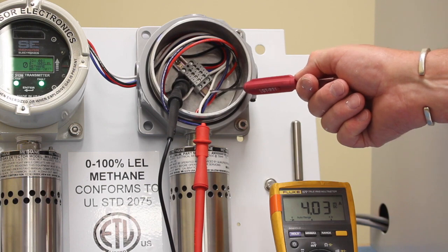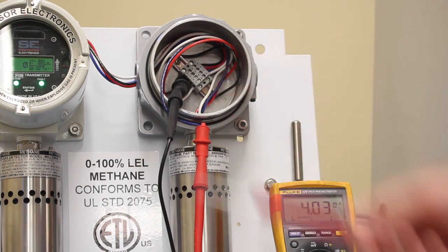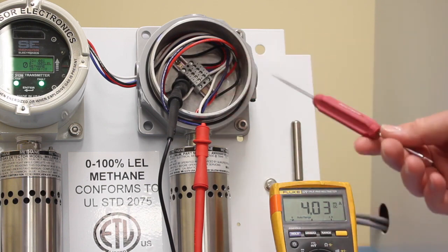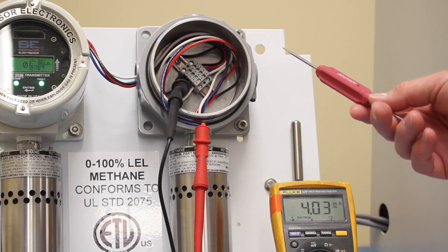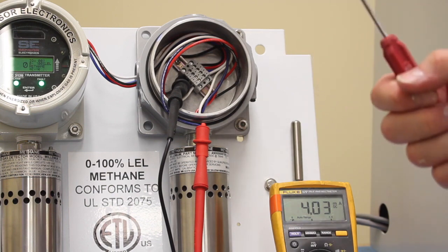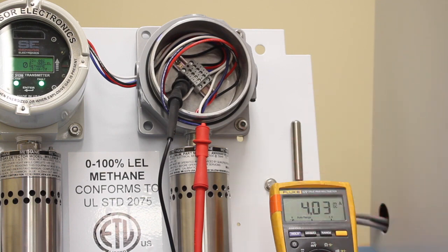Now to zero the sensor, all you need to do is take the calibration wire and connect it to DC common for 10 seconds, and then once that 10 seconds is up, just remove the connection, and then the sensor will actually zero. And that's why I have the current meter hooked up to it, because you'll see it drop down below the 4 milliamps when it's actually doing its zeroing procedure.